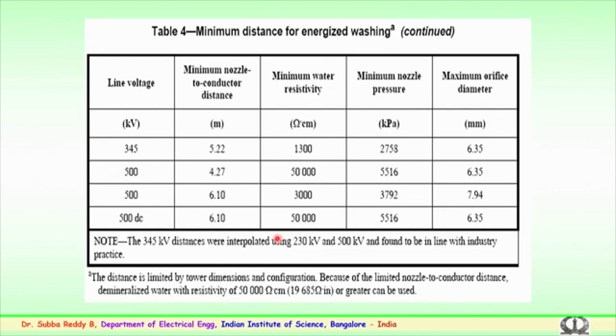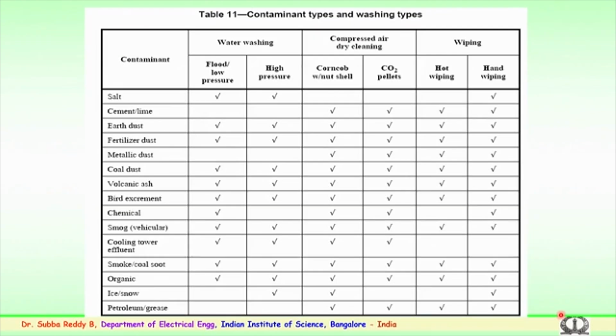So, the distance is generally limited by the tower dimensions and the configurations. Because of the limited nozzle to conductor distance, demineralized water with a resistivity of 50,000 ohm centimeter or greater can be also employed for the cleaning. One such example is for 500 kV DC and 500 kV AC, which is shown here. So, this is typically because of the nozzle to conductor distance which is employed. So, changes could be done the instant where it is being used. So, this is the generalized procedure or the methods which are being employed. Locally, some minor changes depending upon the manufacturer's information can be utilized for proper cleaning.